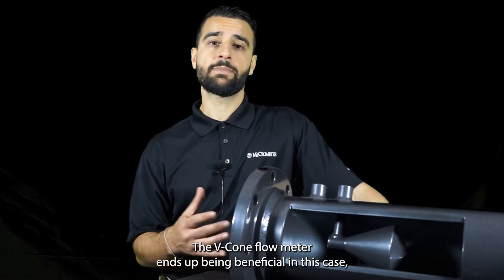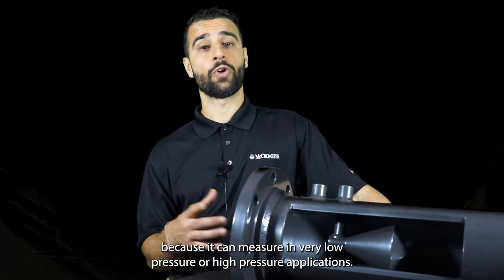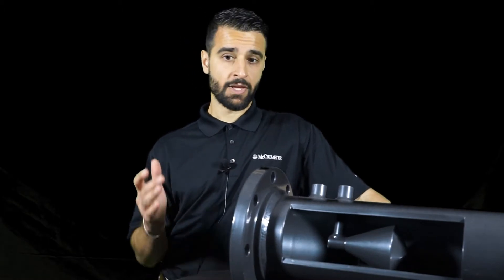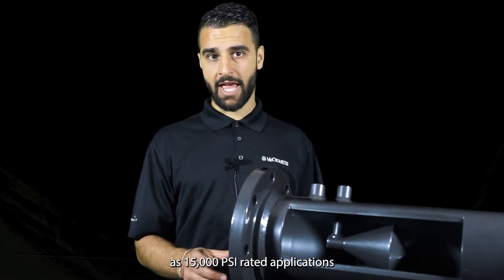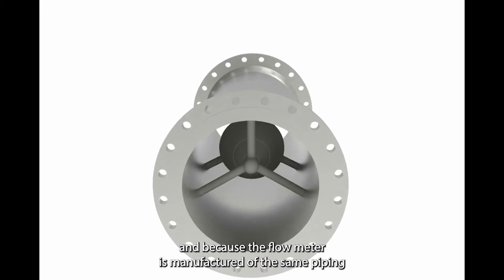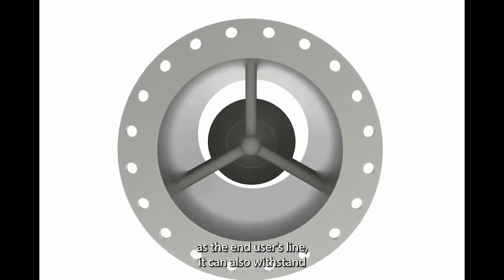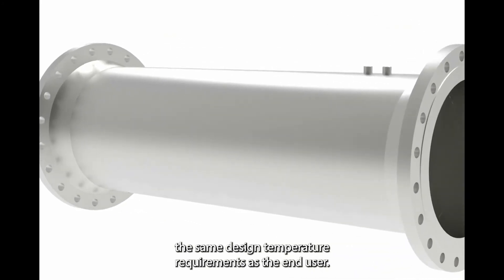The V-Cone flow meter ends up being beneficial in this case because it can measure in very low pressure or high pressure applications. V-Cone flow meters have been built to as much as 15,000 psi rated applications, and because the flow meter is manufactured of the same piping as the end user's line, it can also withstand the same design temperature requirements as the end user.